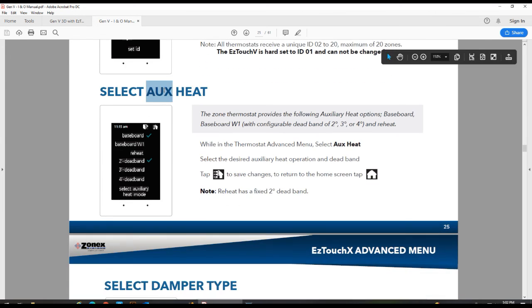If you're utilizing auxiliary heat on the job, such as baseboard heat, you can wire that up to a thermostat, and that thermostat will energize that baseboard heat or electric duct heat, whatever you're running. So make sure you configure this according to that operation. The factory default is baseboard. If you're not running any type of auxiliary heat or baseboard heat, leave the default setting at baseboard. If you're not quite sure, give tech support a call and we can go over it with you and make sure you configure it for the right operation.